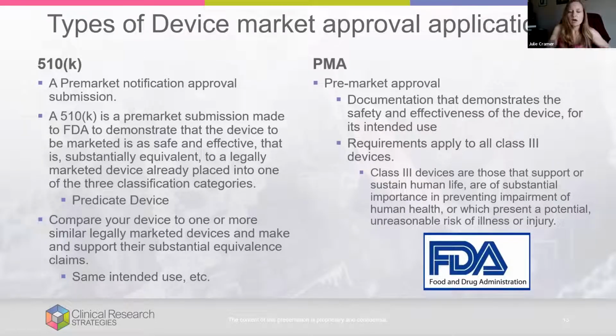Then you have a pre-market approval, all class 3, straight to PMA. This is where you don't have a predicate device and you also are class 3. So here you need to provide documentation that demonstrates the safety and effectiveness of the device for its intended use. So here you have to provide all the clinical evidence because you don't have a predicate to fall back on. You have to provide all of the clinical evidence. So there's many more years of work to be done with a pre-market approval, but there's give and take all the time. Maybe if you're first in class and you're a high-risk device, then there's more to gain by being the first and having to provide all of that initial data.